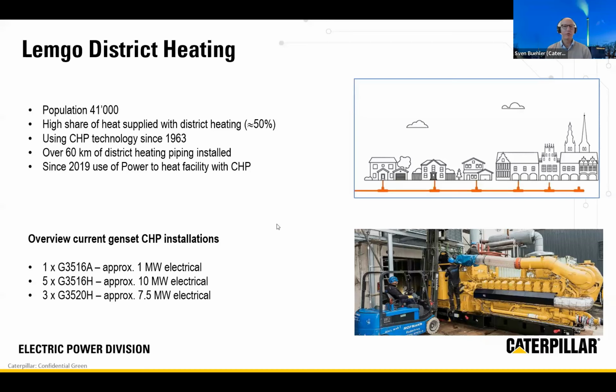The city consumption is around 160 gigawatt hours per year, and the latest and award-winning installation was supplied at the end of 2021 and commissioned in 2022, of 3 G3520Hs. So these are 2.5 electrical megawatt output gas engines that were combined and integrated, which was the key for winning this award, including a thermal solar farm of 5.2 megawatt and a heat pump application to collect heat from the Bega River, which is the local river, providing an additional 1 megawatt of heat.